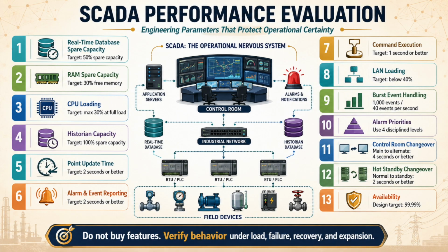This is how engineering replaces assumption. This is how specifications become protective. This is how FAT becomes meaningful. Do not ask only for claims. Ask for a performance compliance matrix, tested architecture diagrams, point count assumptions, scan rate assumptions, historian write rate assumptions, alarm burst results, redundancy switchover records, client loading evidence, network loading calculations, CPU and RAM records, degraded mode behavior, communication recovery behavior, firewall impact, backup impact, cybersecurity tool impact, and proof that historian logging was active during the test.